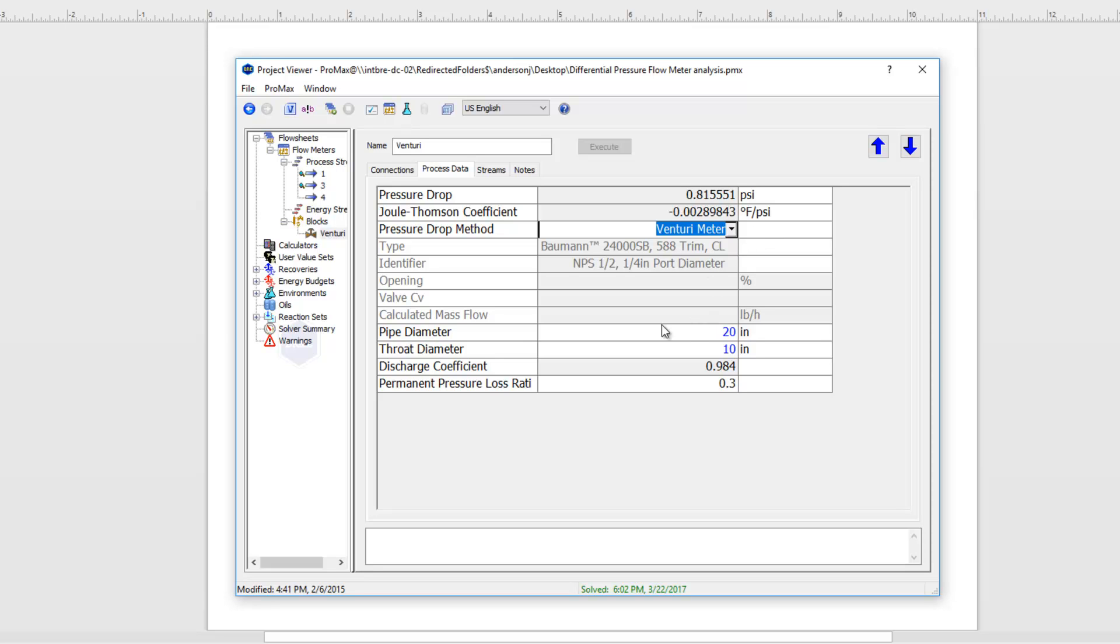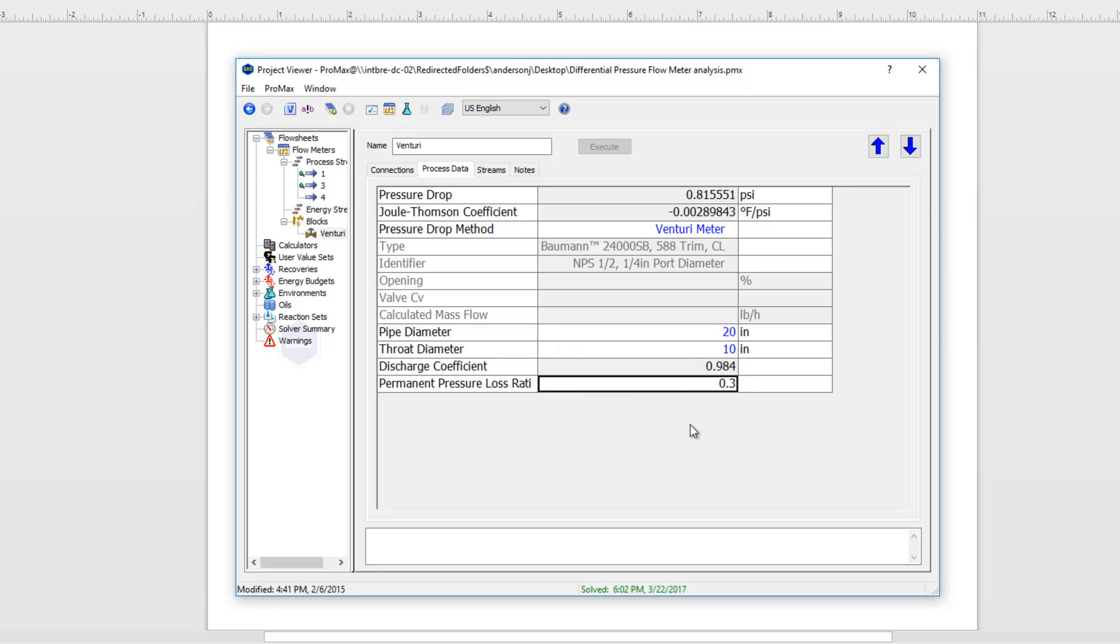With that type selected I can choose again my pipe diameter and throat diameter with my permanent pressure loss specified as well. Up here ProMax is calculating the actual pressure drop that we'll see in our system due to this meter. That way we have the meter actually built into our system.